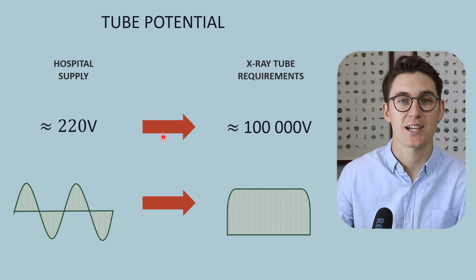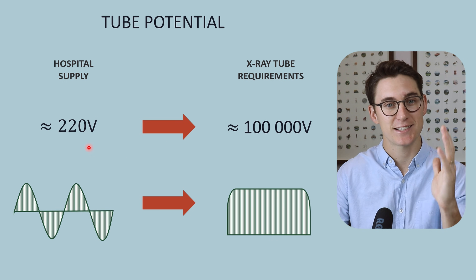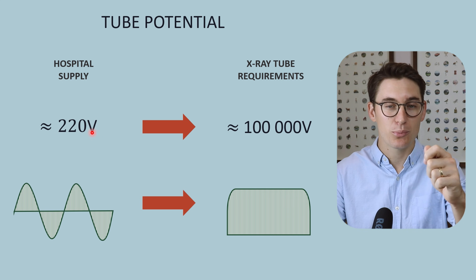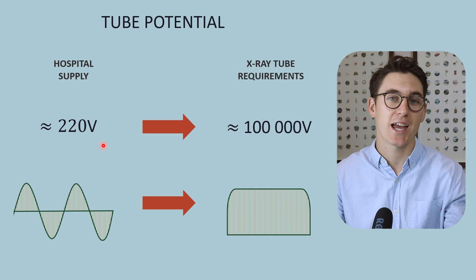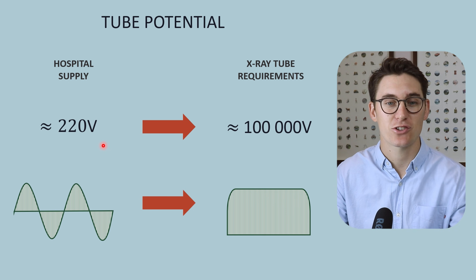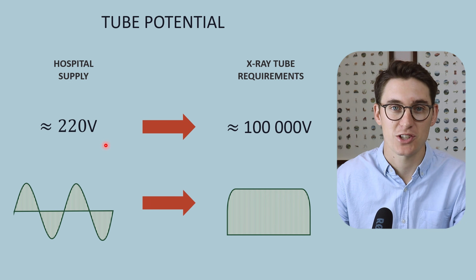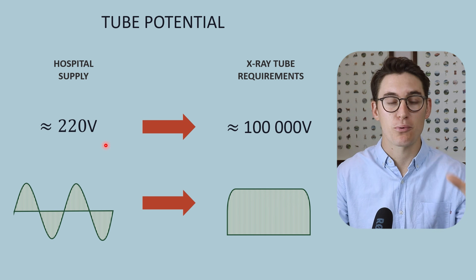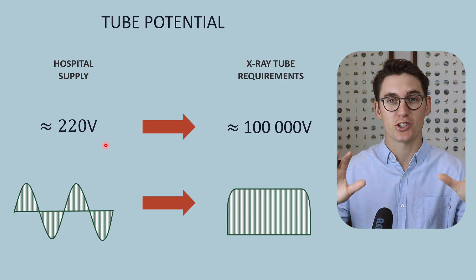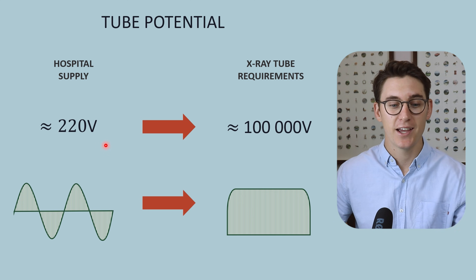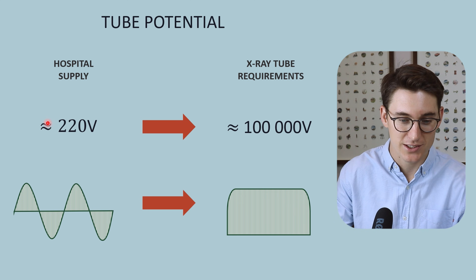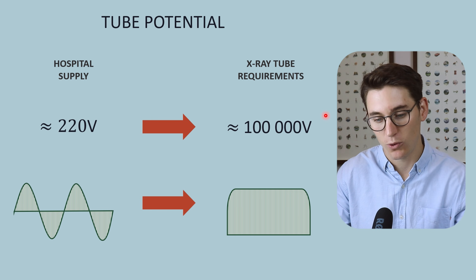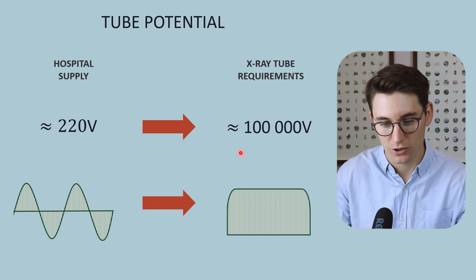Another issue is that the supply is a set voltage, and we want to be able to manipulate that voltage — to change the kVp in our x-ray tube depending on the type of image we are trying to create. The primary and secondary x-ray circuits work together to increase the hospital voltage supply to the order of kilovolts.